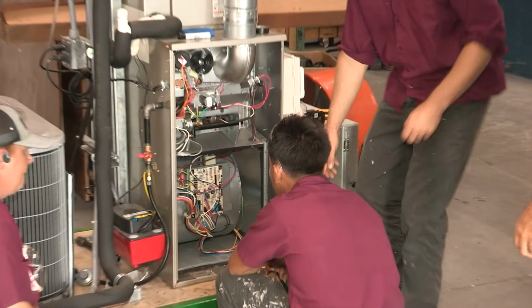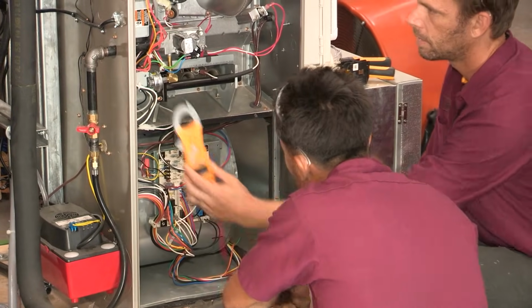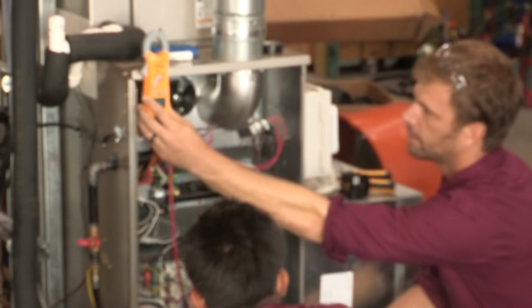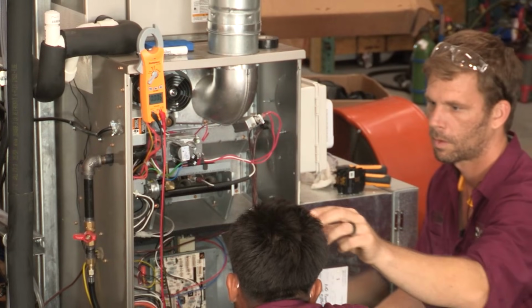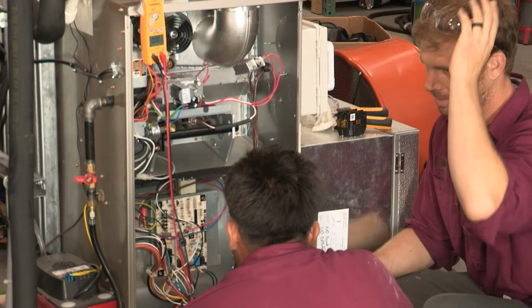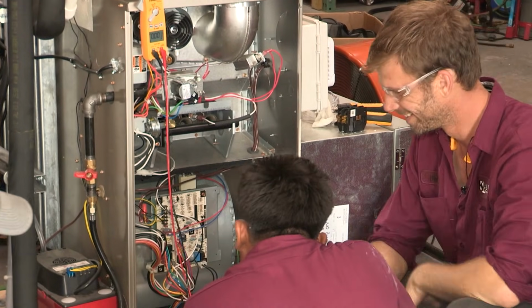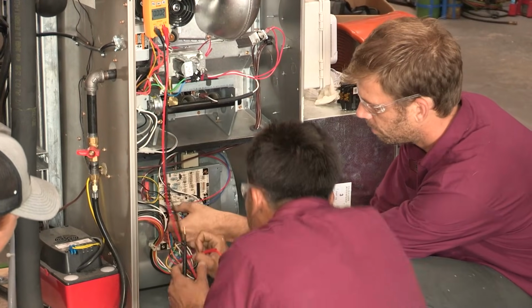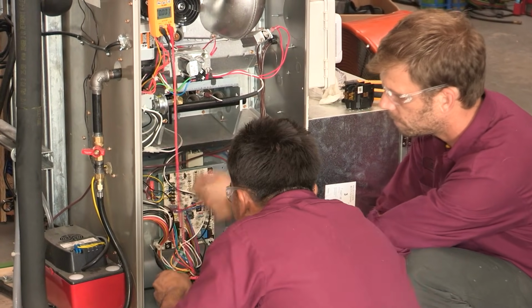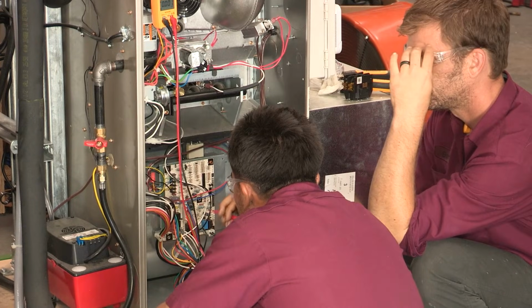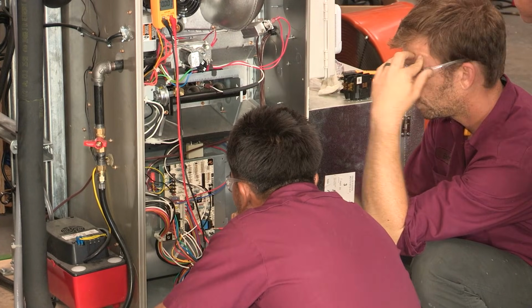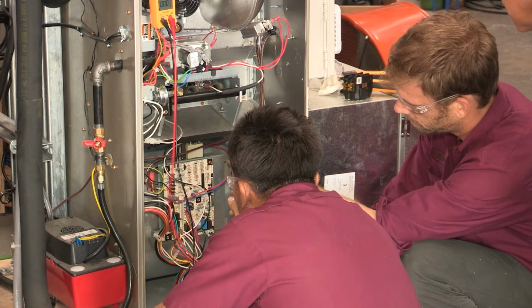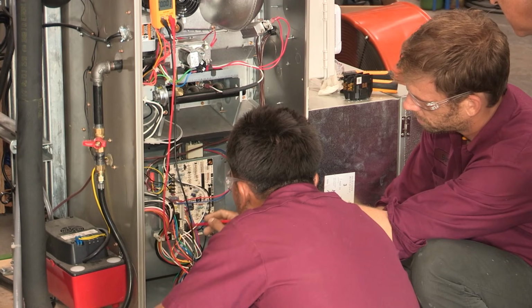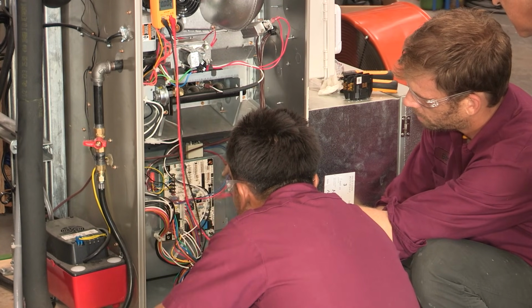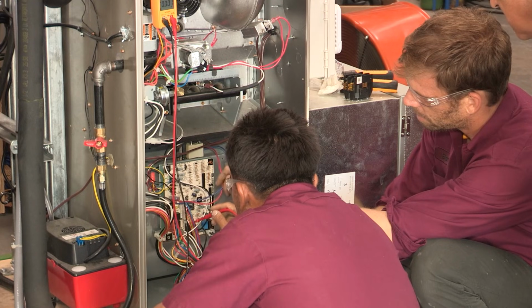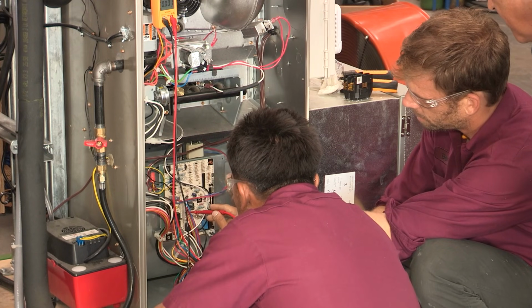So we're switching our meter to what? VAC. All right, so now I'm going to go ahead and check. So which one should I check? What if you're checking for 24 volts between the red and the blue coming out of our transformer here? Yep, so one side is going to be our hot, and the other side is going to be our common.